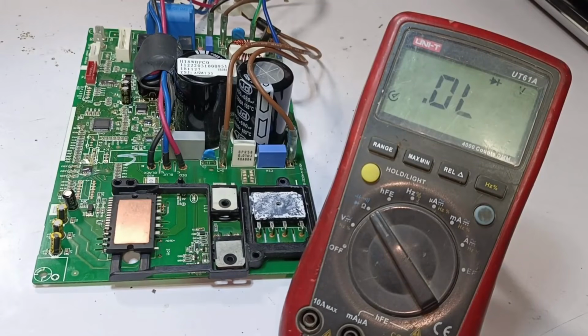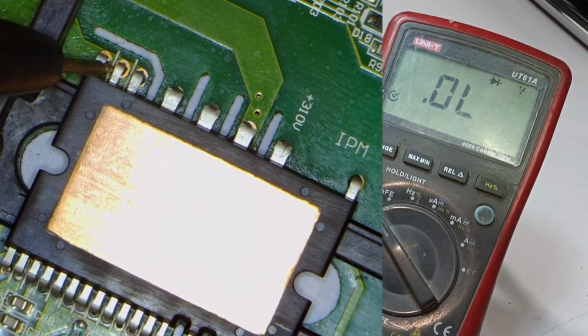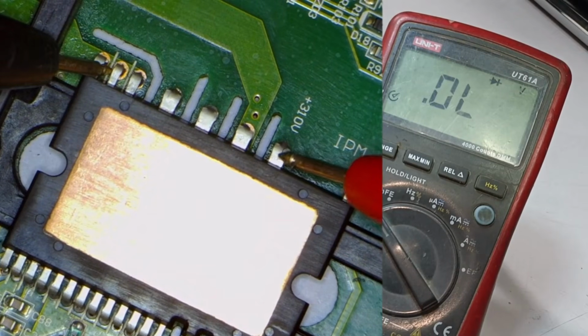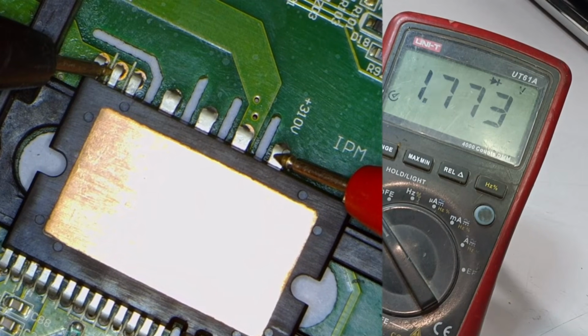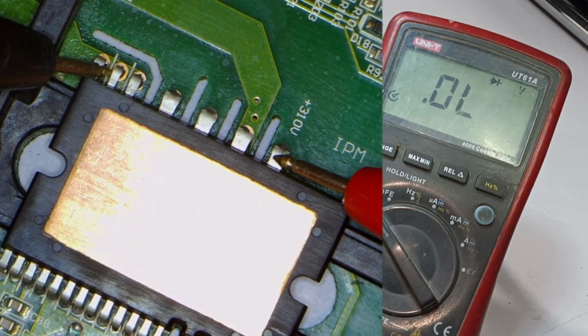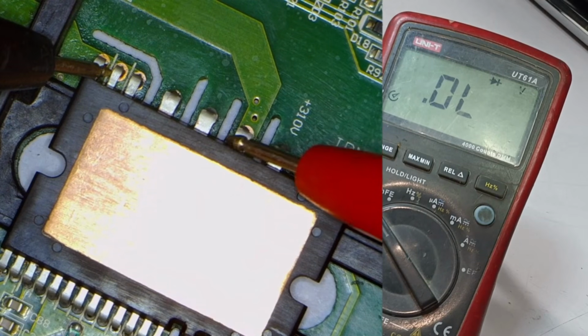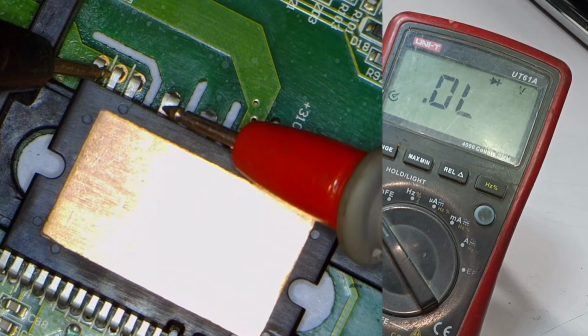Before supplying power, we will test the IPM once. We will place the negative probe on the negative pin and the positive probe on the positive pin. When we did this, we observed a slight voltage drop, which then disappeared. This means the IPM is perfectly fine. Next, there is no voltage drop showing on the U, V, and W pins.